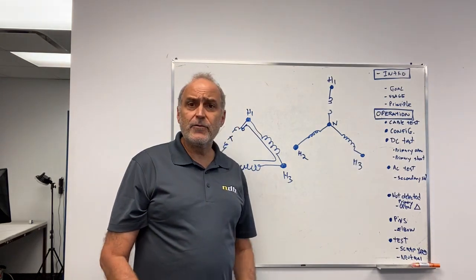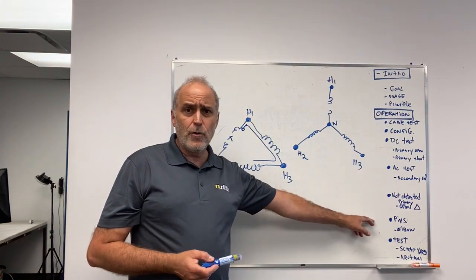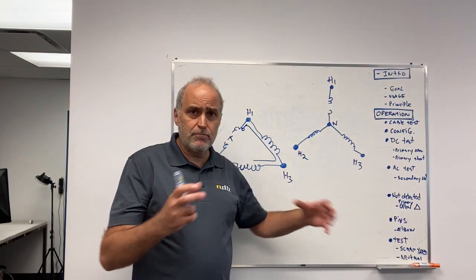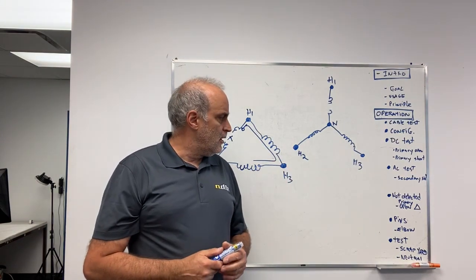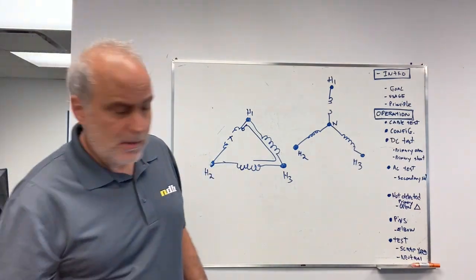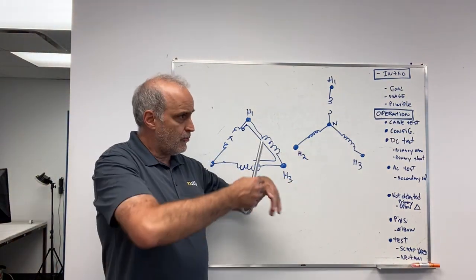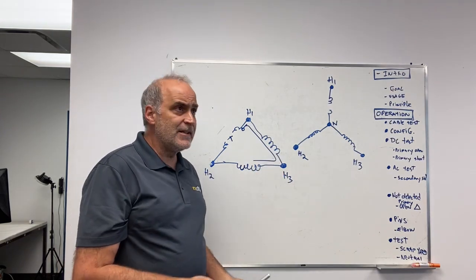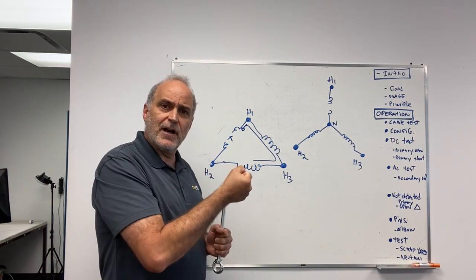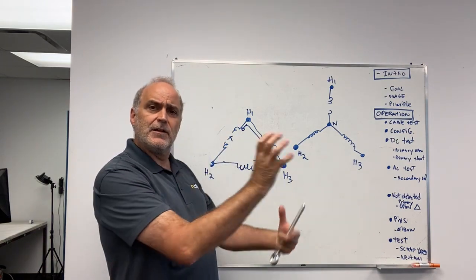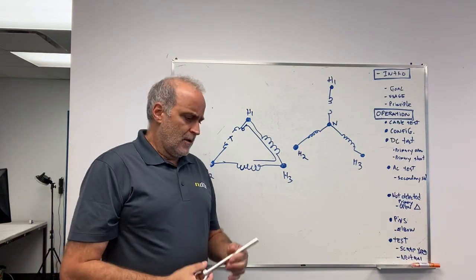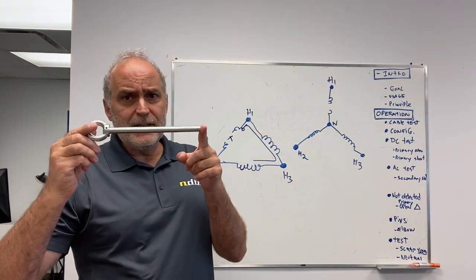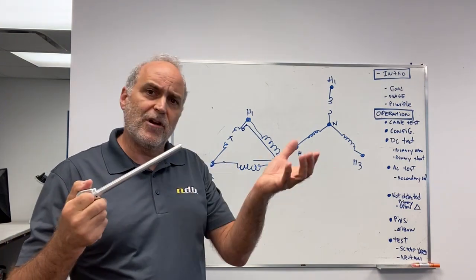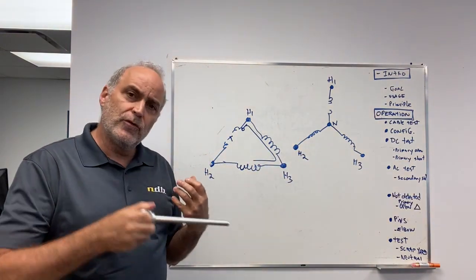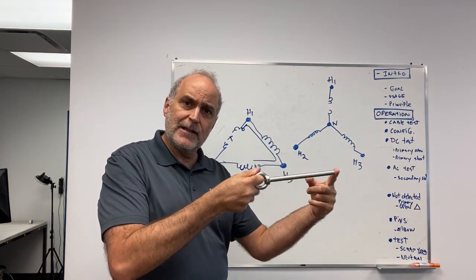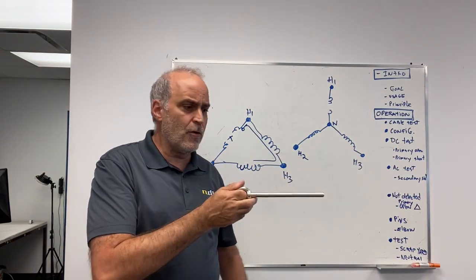This point here is regarding transformers that do not have bushings but have elbow connectors on them. Let's say if elbows are present or installed, you don't have any places to hook the device on the transformer because the elbow is totally covered and it's covering the connector. This is why we are providing pins that fit in the transformer.